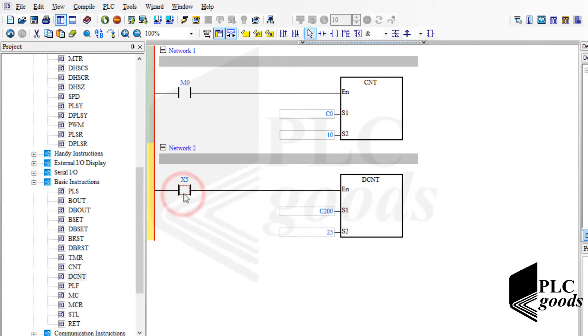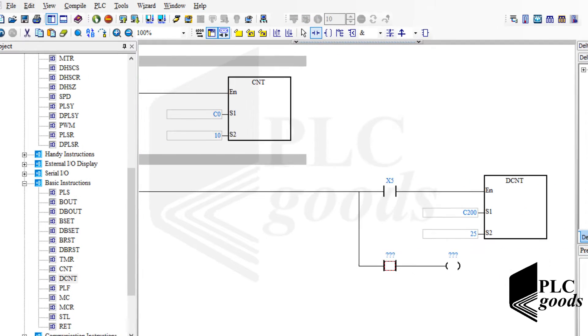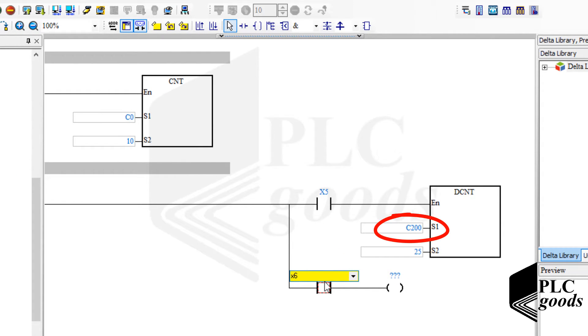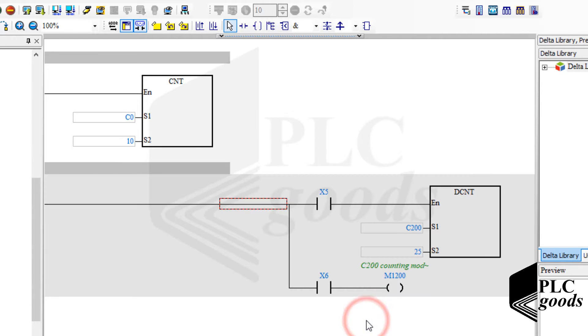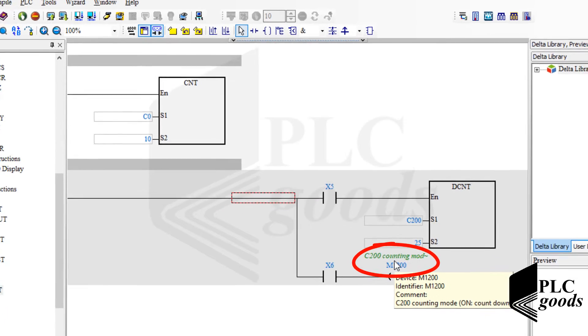32-bit counters can count in two directions, and each of them uses a specific bit memory to determine the counting direction. For example, the related special bit memory for counter C200 is M1200, and this bit memory determines the counting mode of the C200 counter.